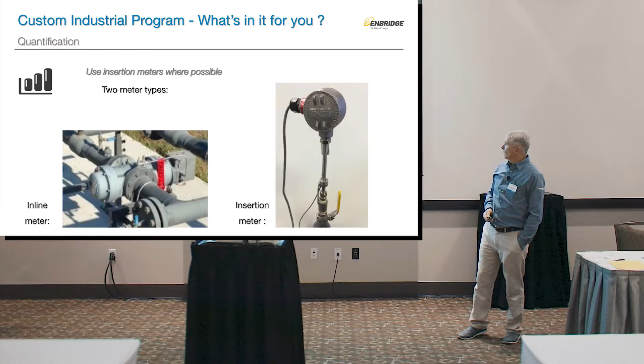With an insertion meter, you weld a weldolet into your pipe, drill a hole, and put an isolation valve in the weldolet, so you don't have to have the meter right away, you can just prepare it. When you're ready, you open the isolation valve and put the insertion meter in. This can be done hot, meaning you don't have to take the equipment down, which is a great advantage for people who need to run 24/7.